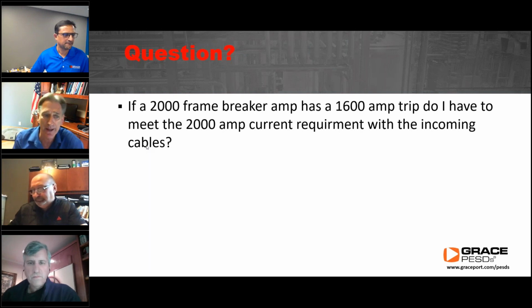A lot of times these sections are overlooked. Well, B talks about adjustable trip circuit breakers. And B says the rating of adjustable trip circuit breakers having external means for adjustment. So if it's a modular type where a component is put in the side or the back after it's been pulled out, this wouldn't apply.